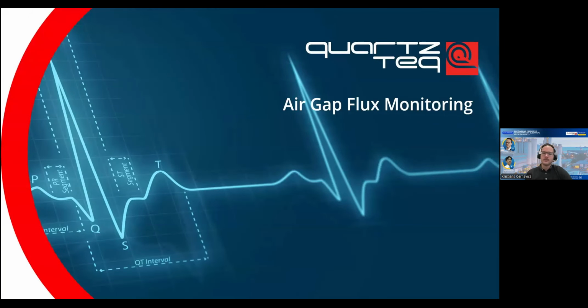So now we covered the main part about condition monitoring of the partial discharges and the types of online and offline monitors and sensors, and this was all essentially connected with the stator winding tests. But as you remember, in one of the first slides in the beginning, I also showed you that the two other main types of problems that happen in machines are connected either to the rotor windings or also the bearings and the shaft. So let's look at the next characteristic we can monitor, which is called air gap flux monitoring.